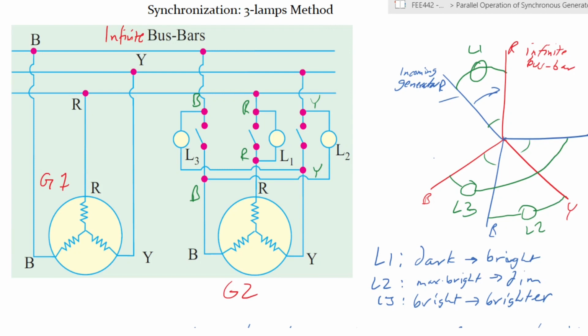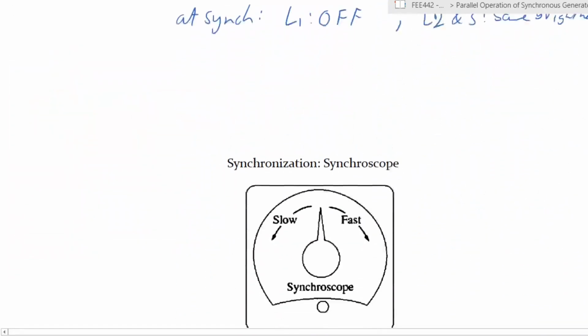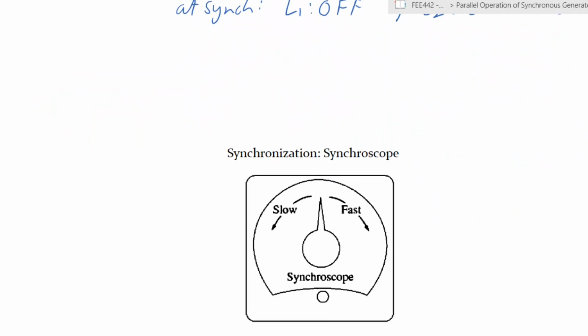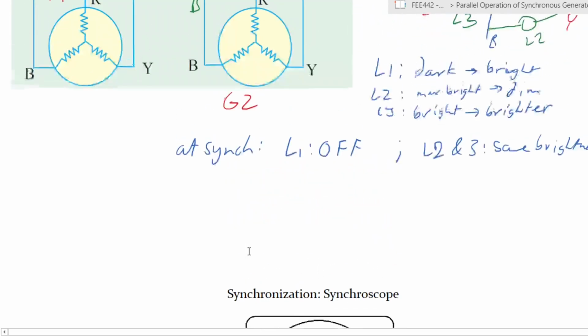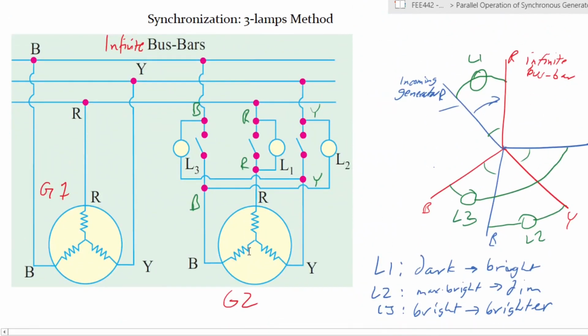But nowadays, in the area of digitalization, generally what you would find is a machine called a Synchroscope that automates this process. We won't go into how it operates, but generally a Synchroscope is a meter or some kind of indicator instrument that literally shows you if your generator is fast or slow, and you would need to either slow it down or speed it up to match the positions of the infinite busbar that you want to connect to. I may not have mentioned that the process of synchronization involves speeding up or slowing down the generator's prime mover so that it is matching the speed and frequency of the busbars.